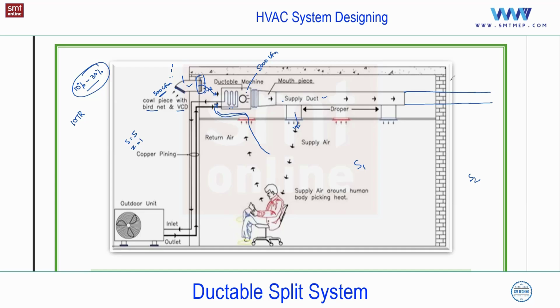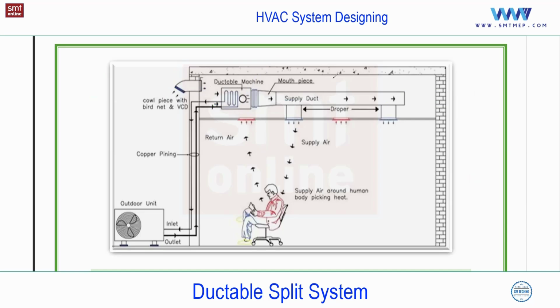Okay, so generally, technically, if you talk about exhaust, we require an exhaust fan or an opening for exhaust. But in actual practice, if it is residential or an office, you'll not find a separate exhaust fan, because whenever you open the door, because of positive pressure, the exhaust will happen. We'll discuss more about this fresh air exhaust system, how to balance and all. At this level, we are providing say 500 CFM fresh air. The remaining from the return, again 5000, is supplied through this duct to the spaces. Got the idea about this ductable split? The concept of this ductable split system.